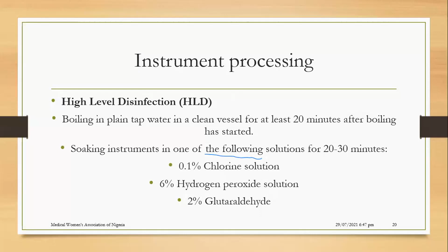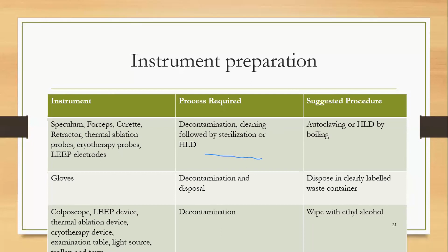So this table somehow summarizes what we need to do. For speculum and forceps, which is usually what we use, you decontaminate, you clean, followed by sterilization or high-level disinfection. If you have an autoclave, good and fine, you can sterilize. If not, you go for high-level disinfection. For gloves, ideally, we are to decontaminate. If you finish using your gloves, you are not just supposed to remove them. Even removing the gloves, there is a way you are supposed to do it, so that the dirty part, the part that you use on your patient, doesn't come in contact with your skin, so that you remove one glove inside the other glove and then dispose of it in a clearly labeled waste container. Then for the thermal ablation device, we decontaminate and then we wipe. We don't autoclave it, we don't put it for high-level disinfection. All we do is decontaminate and then wipe with ethyl alcohol or methylated spirit.